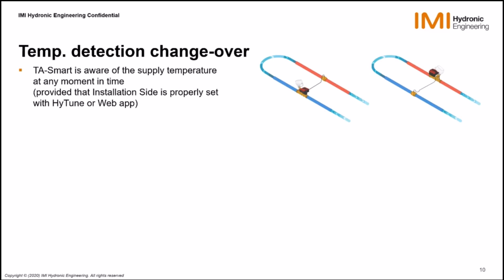Okay, the next one is something really new for us in terms of changeover, and I think for quite a few other manufacturers. I've not seen many things like this, but when you think about it, TA-Smart is aware of the supply temperature at any moment in time, the supply water temperature, naturally. This is the case provided, of course, that you have properly set the installation side of TA-Smart. So if TA-Smart is installed on the supply like this, then the valve knows that the remote temperature sensor is on the return. Then the valve knows that the supply is the local one, and we can therefore really know which one we have to look at in terms of supply.